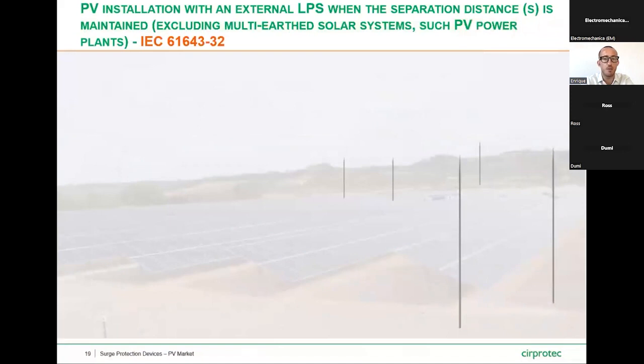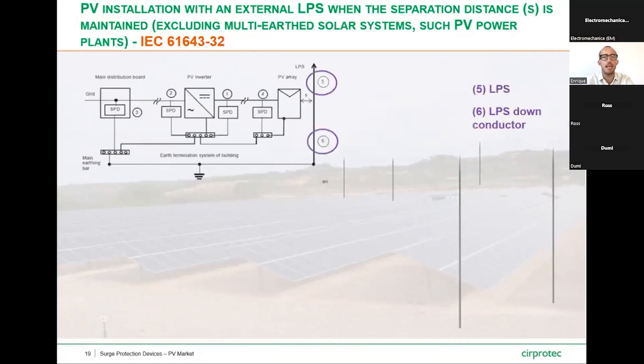Let's move on to the second PV installation type defined as per the standard, with an external LPS in place when the separation distance is maintained. I remind you that this case is excluding the multi-earth solar systems such as PV power plants. In that case, we do have in the location 5 the LPS lightning rod, and in the location 6 the LPS down conductor.